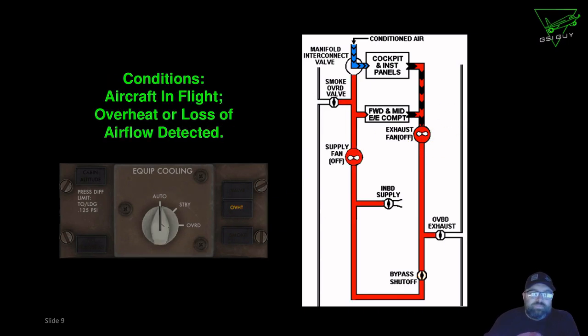Now, separate day, new jet, new day, new problem, right? So now we've got what appears to be an overheat. So we're in the auto position. Remember, our valves are all closed. We're off the ground. So our conditioned air is coming in, but now we don't have the exhaust fan pulling that air through. Okay. So we overheat because there's no airflow. We're literally putting conditioned air in there, but it's not getting pulled through the system like it normally would.